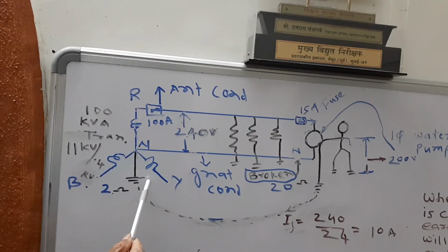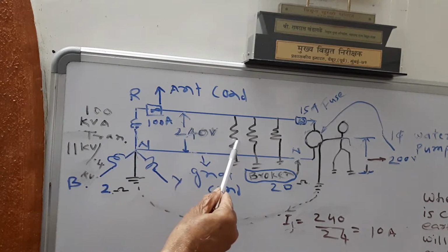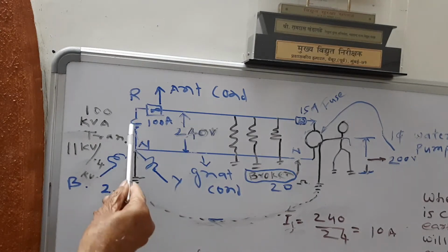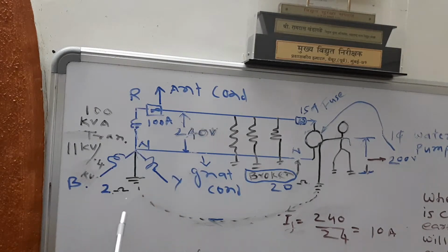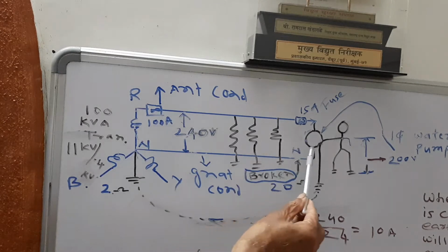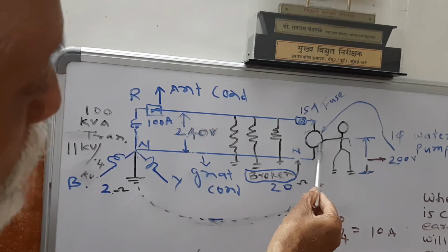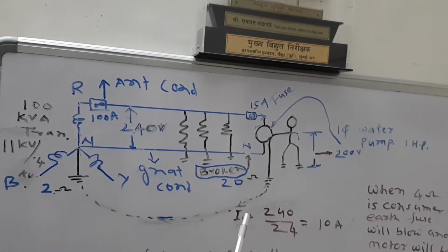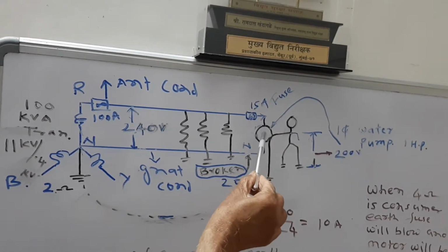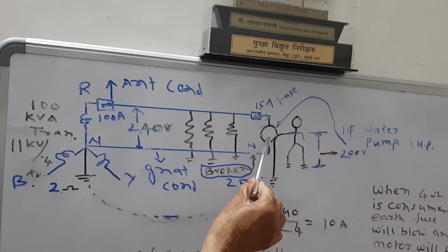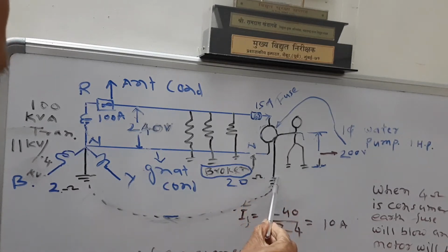Friends, this is the LT winding of a distribution transformer having neutral double earth, neutral value 2 ohm, and across this coil these are the loads 1, 2, 3, and 4, and the phase to neutral voltage is 240. Here the fuse is 100 ampere, and this is a water lifting pump of 1 HP, and the fuse is of 15 ampere. This motor gets short circuited and the short circuit current leaks to the frame, and this frame is earthed here, and the earthing value of this frame is 20 ohm.